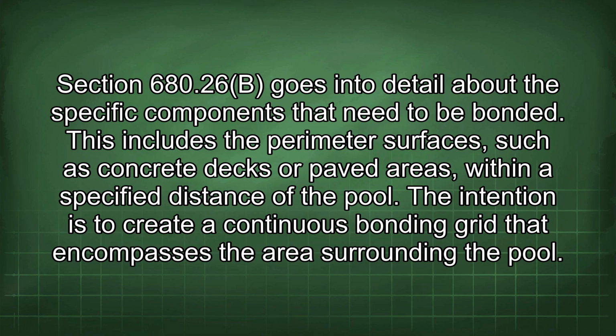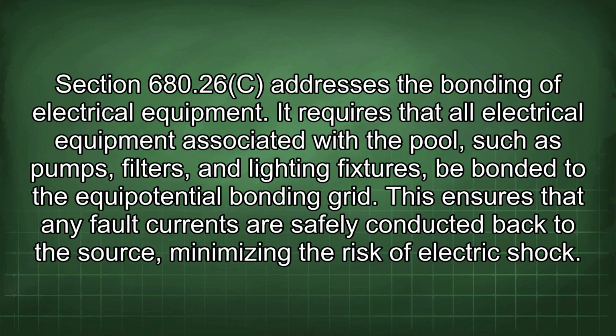Section 680.26b goes into detail about the specific components that need to be bonded. This includes the perimeter surfaces, such as concrete decks or paved areas, within a specified distance of the pool. The intention is to create a continuous bonding grid that encompasses the area surrounding the pool. Section 680.26c addresses the bonding of electrical equipment. It requires that all electrical equipment associated with the pool, such as pumps, filters, and lighting fixtures, be bonded to the equipotential bonding grid.